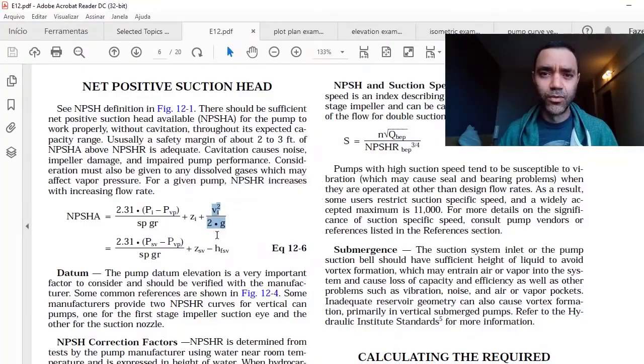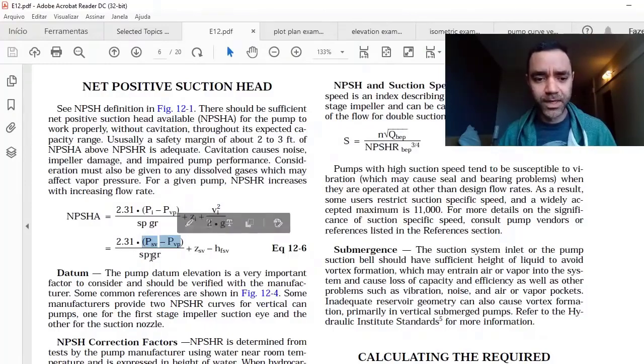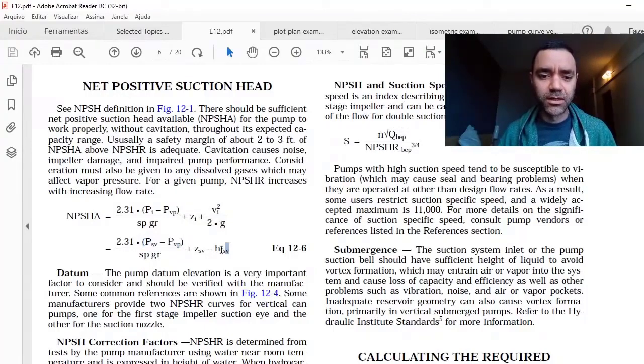Because you will see how it influences the NPSH. And we can use the pressure in the suction of the pump, the vapor pressure also, and specific gravity, and consider the losses that you have in your pipe system at the suction of the pump.